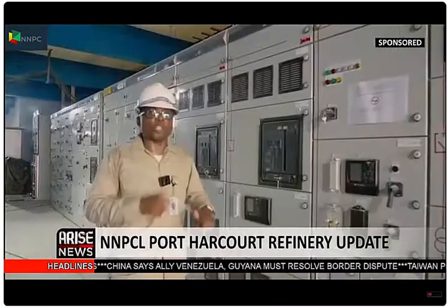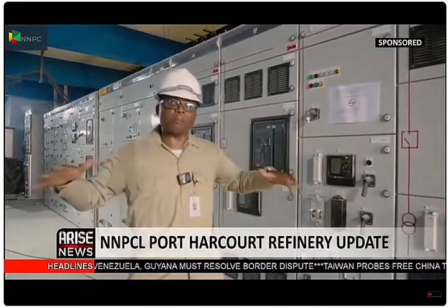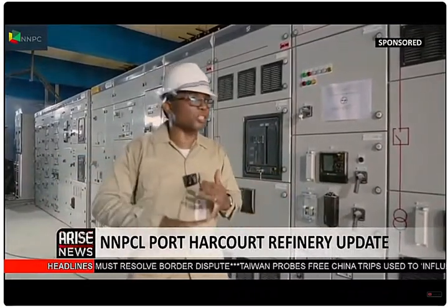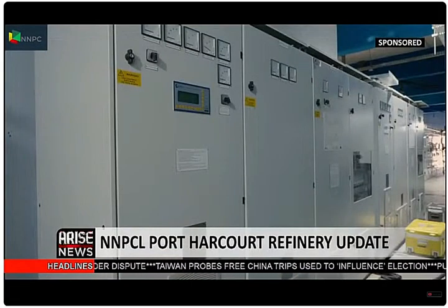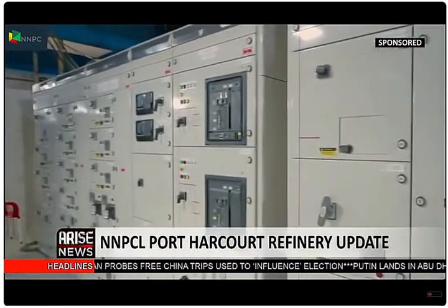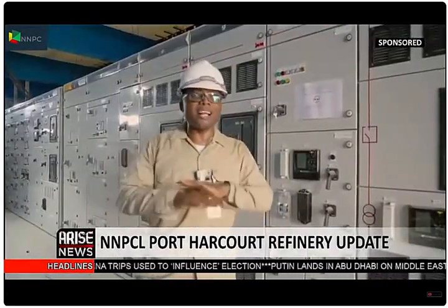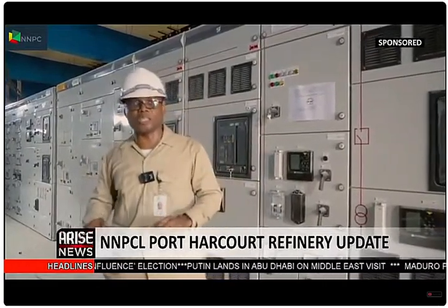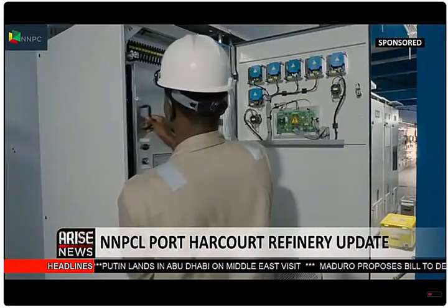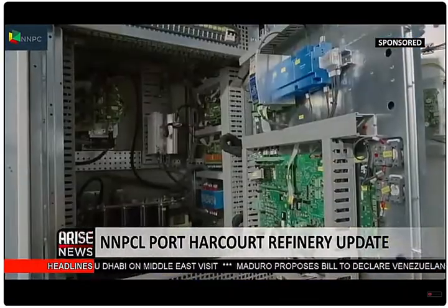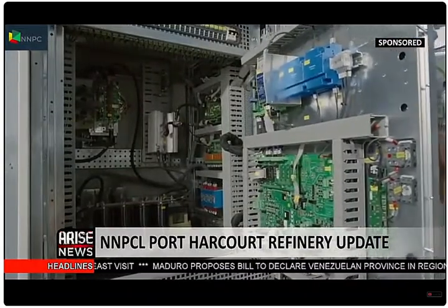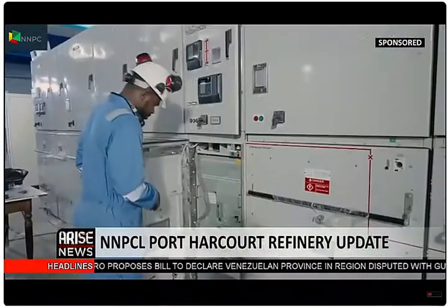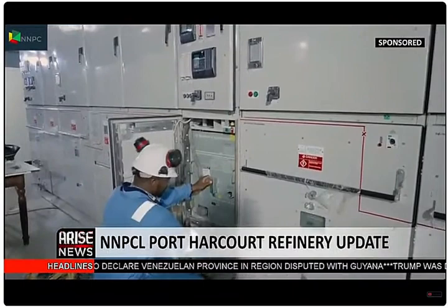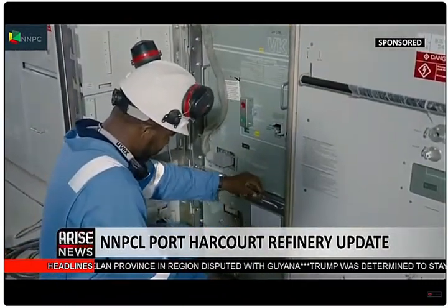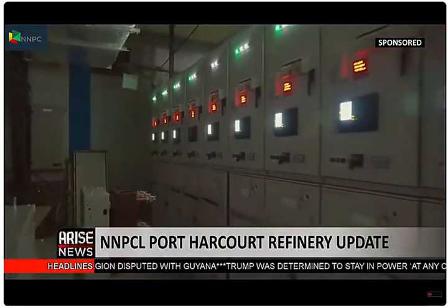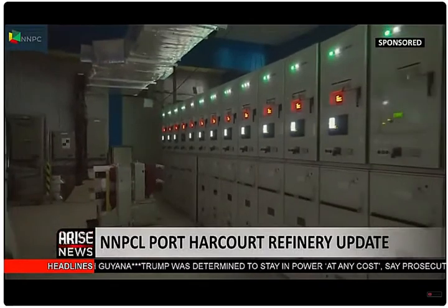Power goes everywhere else. Okay, so during this rehabilitation project, all the equipment in this substation have been taken out. The transformers, the switch gears, the bus bars, all of them, and even the EPMS, that's the electronic power management system, has also been introduced. Everything here is brand new, latest technology, and up to date. Though brand new, a few modifications were made to improve its protection system. This was done to prevent a recurring problem in the past where a fault downstream could affect the substation. Cable termination is ongoing for other substations. Currently energized by generators, it will be powered by gas turbine generators in mid-December.